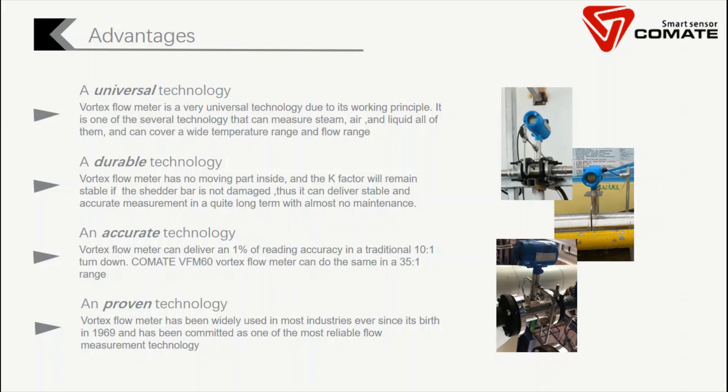Third, it's also a very accurate technology. A traditional vortex flow meter can deliver 1% of reading accuracy in a traditional 10-to-1 turndown ratio. COMATE VFM60 can do even better — the same accuracy in a wider range of 35-to-1. Fourth, it's also a proven technology. Vortex flow meters have been widely used in almost every industry since their introduction in 1969 and are one of the most reliable technologies.